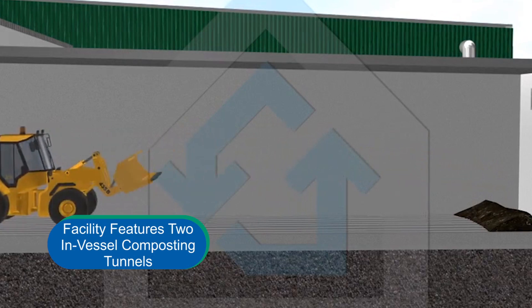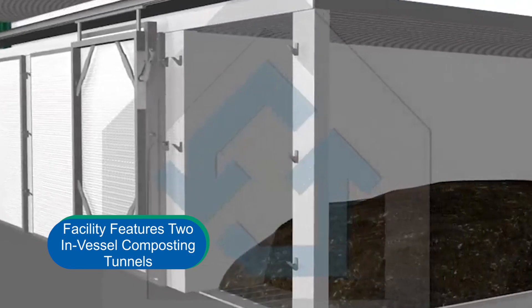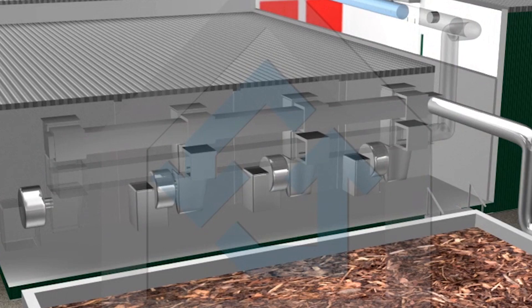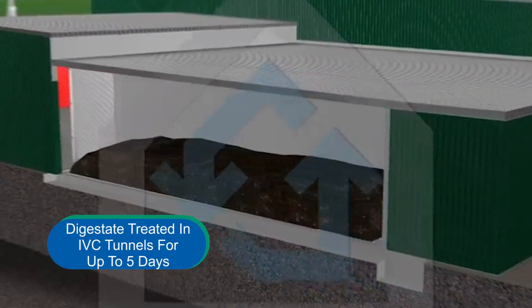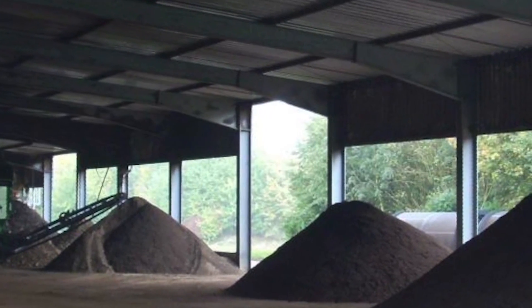The Blue Line facility features two in-vessel composting, or IVC tunnels, to treat digestate that is removed from the SmartFerm system. The IVC tunnels are specially designed to rapidly drive odor-causing ammonia from the digestate material through the precise control of air flow and temperature. The digestate will be treated in the IVC tunnels for up to five days before it is unloaded and hauled to a regional composting facility for final maturation and screening.